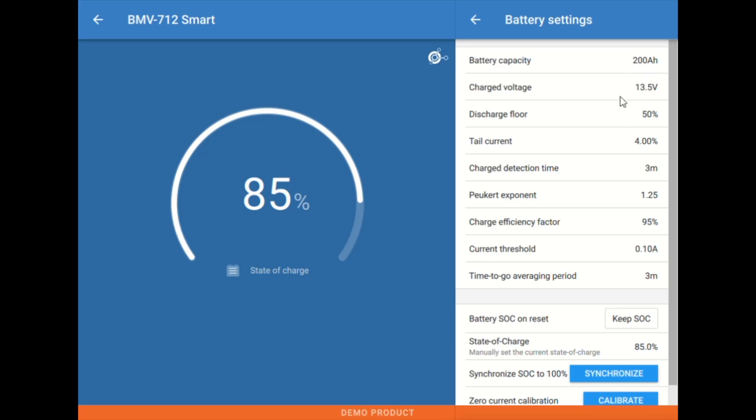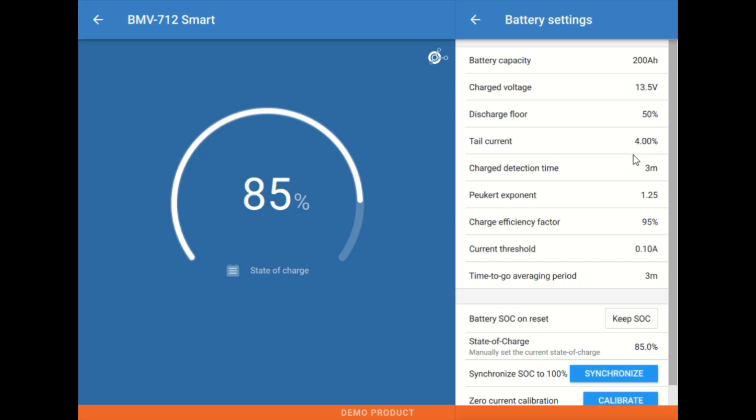So when the amps drop below, in this case 4% of the total, that's used as a signal for the meter as a trigger that the batteries are full. This is usually not something we're going to mess with most of the time. This 4% value, unless we have some extreme circumstances, is adequate here.